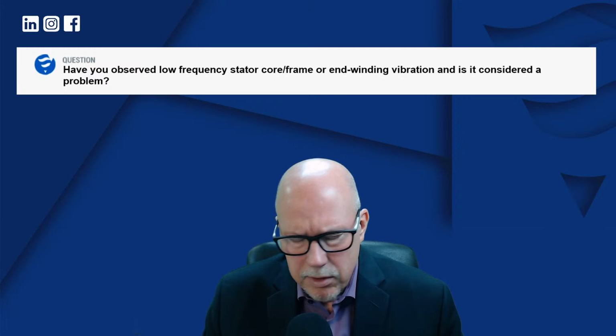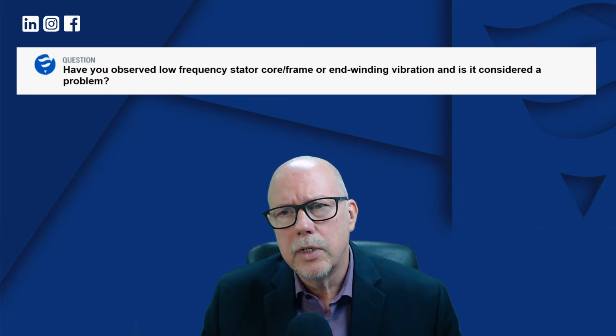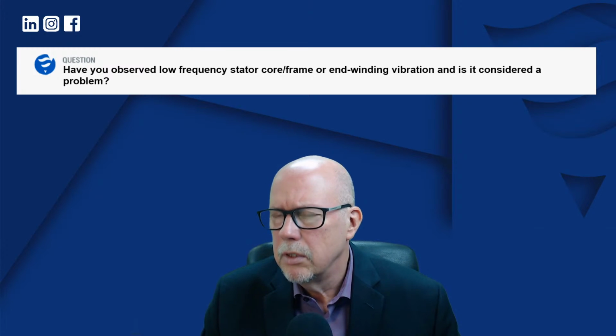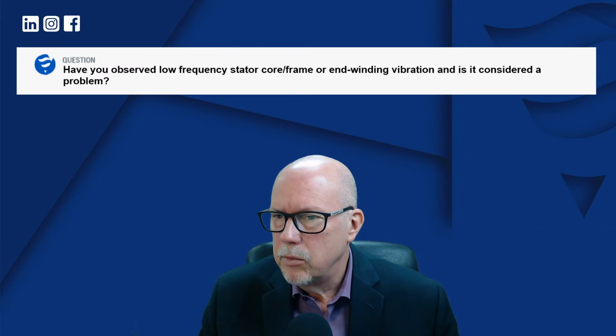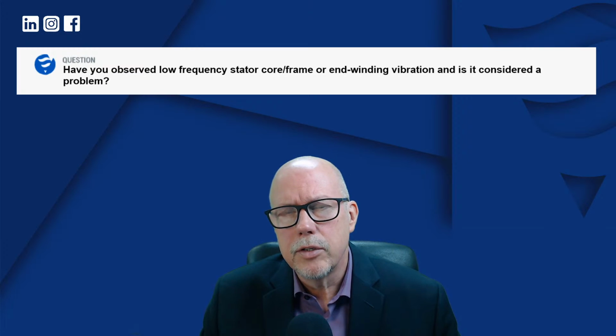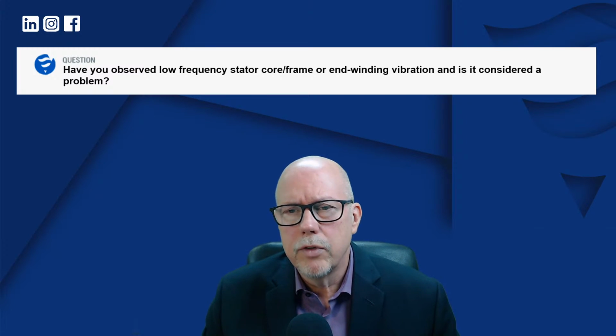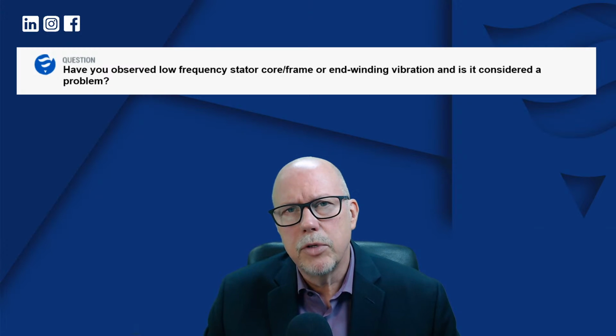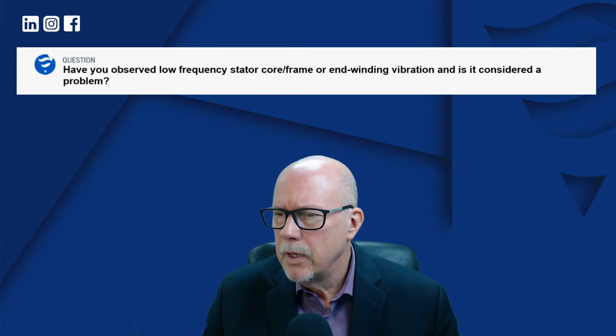I have another case, an interesting case that was in the US, where they had older type sensors from a manufacturer, very old, and when they did some major work on their stator, they removed all that and they bought our system and put it in there, and all of a sudden they had high vibration levels that were being picked up.